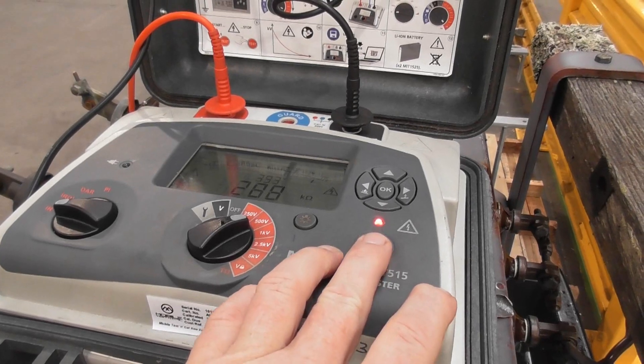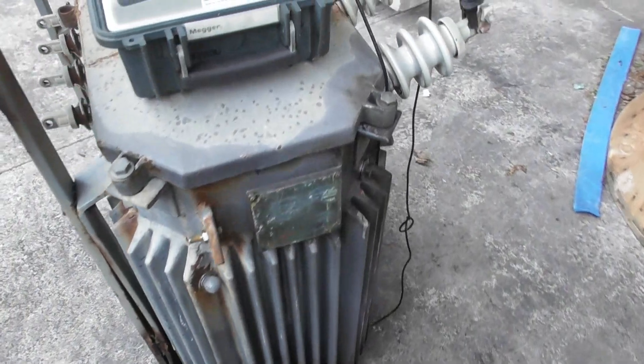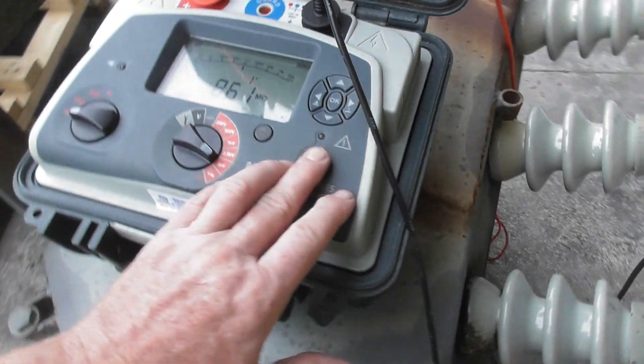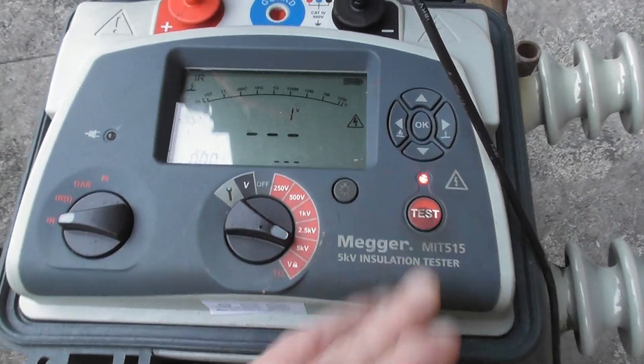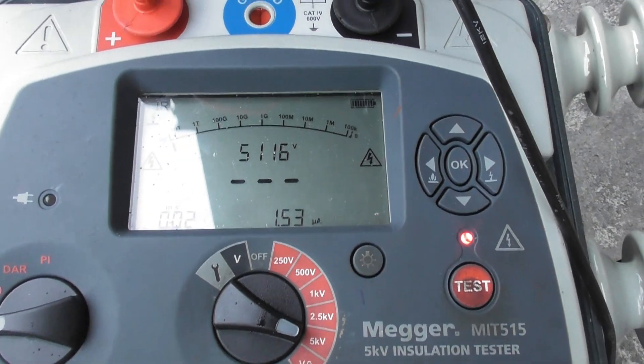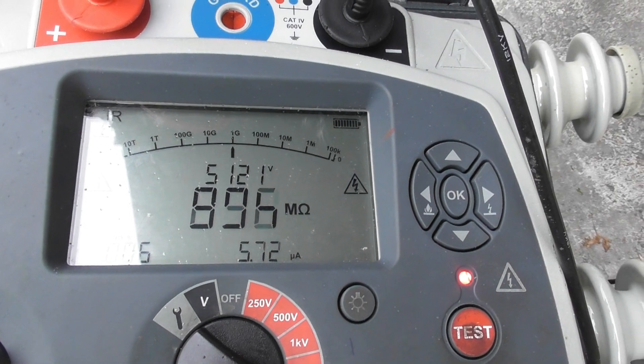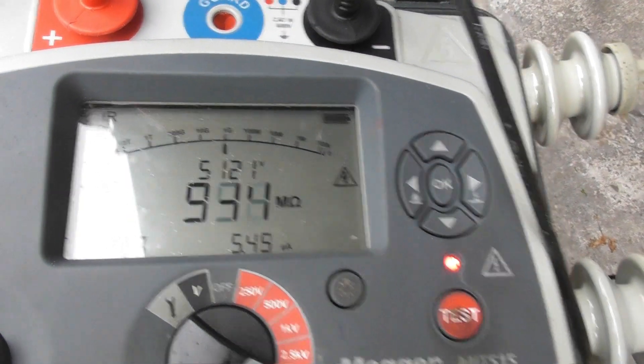The energized device. For comparison, I'll do this other transformer — similar type. I don't know if this has blown up or whatever, but I'll give it the test. Energized device. That's holding 5kV easily on the HV winding.